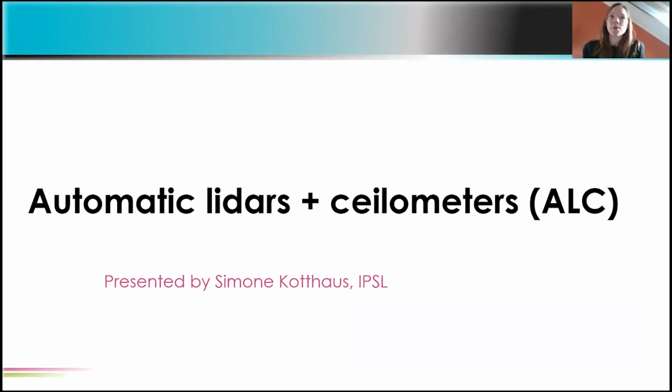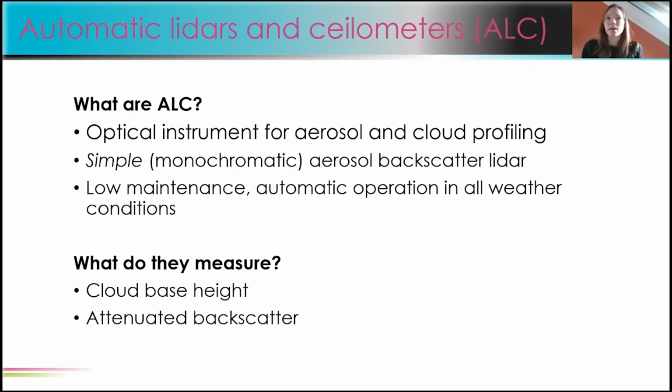I will go on with automatic lidars and ceilometers, that are the next system we want to introduce. These are optical instruments that we use for aerosol and cloud profiling. We can think of them as simple aerosol lidars, usually working on one single wavelength.